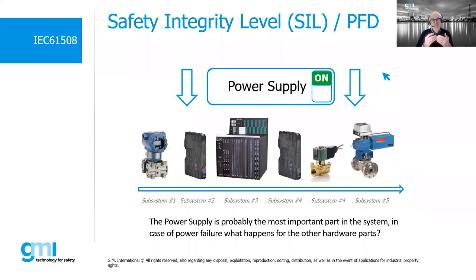Well, now let's start by introducing the concept of a SIS. A SIS is a set of subsystems that make up the safety loop. Within this safety loop, we have field devices such as a transmitter or sensor, which allow us to control, detect, and measure variables in the field, such as temperature, pressure, or other. They are driven by barriers or isolators that provide for limiting the current towards the hazardous area or to isolate the field instrument. And in turn, the signal sent by the field loop will be acquired, managed, and interpreted by what is the brain of the SIS, the PLC or DCS system, which will decide on any action to be taken to make a plant safe.